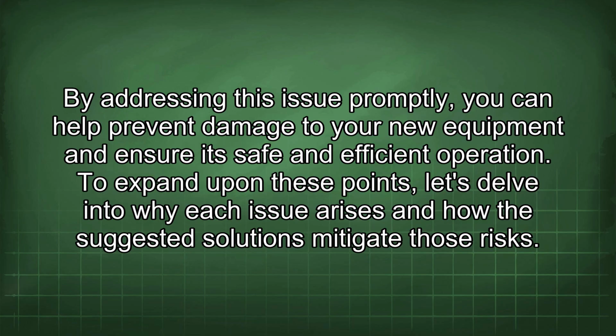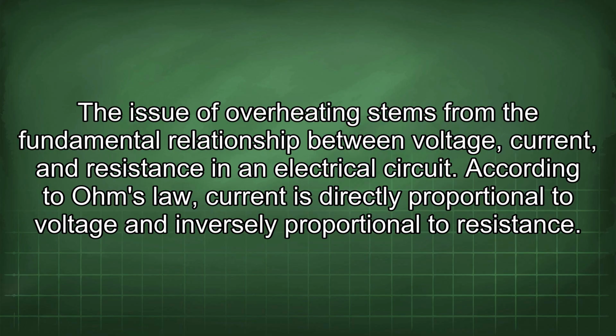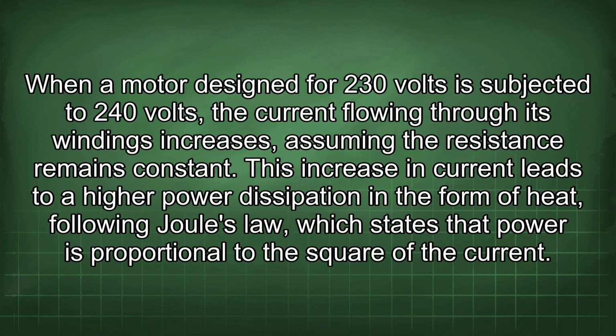operation. To expand upon these points, let's delve into why each issue arises and how the suggested solutions mitigate those risks. The issue of overheating stems from the fundamental relationship between voltage, current, and resistance in an electrical circuit. According to Ohm's law, current is directly proportional to voltage and inversely proportional to resistance. When a motor designed for 230 volts is subjected to 240 volts, the current flowing through its windings increases, assuming the resistance remains constant. This increase in current leads to higher power dissipation in the form of heat, following Joule's law, which states that power is proportional to the square of the current.